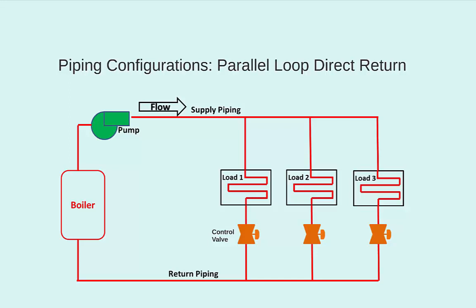So to prevent load 1 from getting more than its fair share of water flow, we have to install what is called a balancing valve. This is just a valve, which we close part way to create more resistance to flow through that particular path. Now, more flow will want to go to the coils located further from the pump. To prevent coil 2 from getting more than its fair share of flow, we would also need to put a balancing valve there. It just probably won't be quite as closed as the balancing valve located at coil 1. So theoretically, we could install these balancing valves and adjust them until we got the correct amount of flow, 10 GPM, through each coil. But if coil 3 was excessively far away, this process could become very difficult and time-consuming.